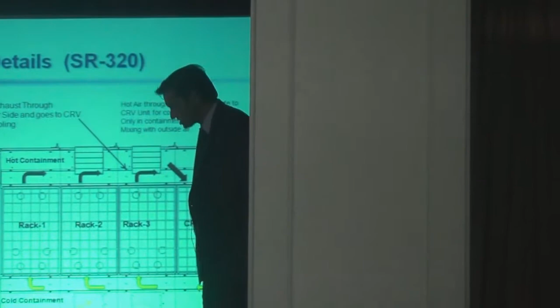Now, we have one more technology - if you're not going for redundant cooling, but your cooling goes down, we have a sensor that automatically opens the door. Typically in a data center, when cooling goes down, the manager or a local person goes and opens the door and puts some exhaust fan or table fan. Here, you don't need to do anything - the moment the cooling goes down or there's maintenance, it automatically opens the door and enables the exhaust fan so it can provide cooling to your server or IT equipment. Those kinds of standards we follow.